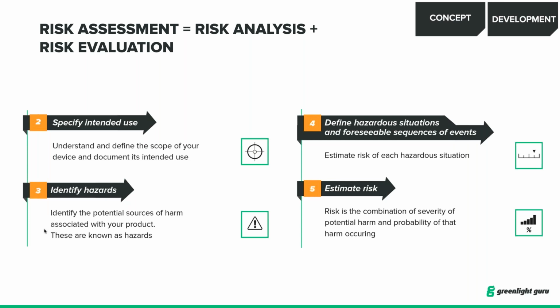I think it's important from a risk management perspective, because it really defines the guardrails or the scope of your risk management activities for this particular product. There are points in time where it is good to think about misuse, either intentional or unintentional misuse of your product, outside the confines of the intended use scenario.